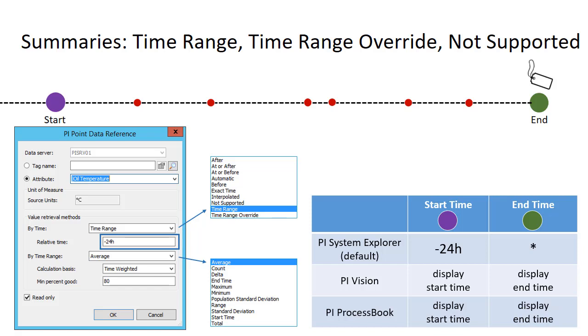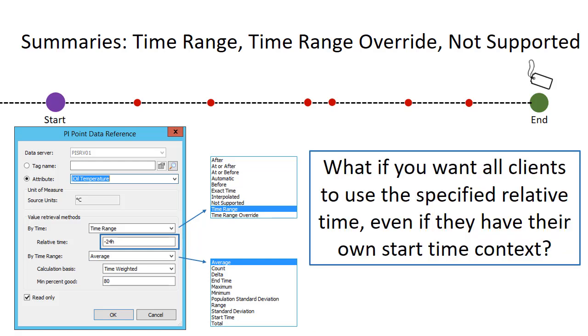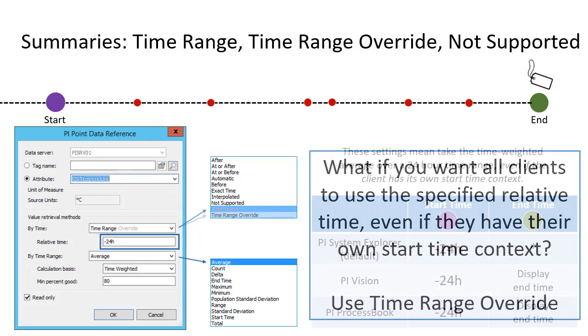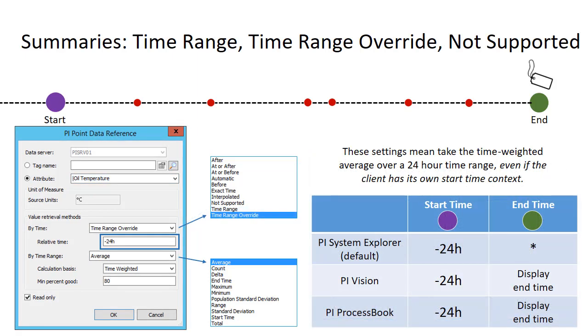These clients will use the start and end times of the display. So when using time range, the relative start time is used only if the client doesn't have its own start time context. If you want PI Vision and PI ProcessBook to also use 24 hours for the average even if the display time range isn't 24 hours, this is why you use time range override. In that case, the end time of the summary call refers to the end time of the display, but the summary call is forced to be the end time minus 24 hours.